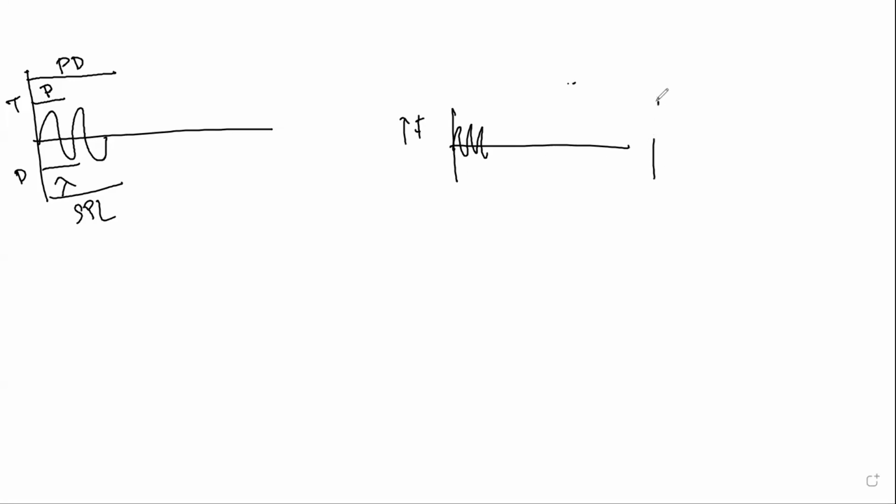So then we have a low frequency. Remember, long, low frequencies. Long, low. This is going to take more time to occur, so its pulse length, the distance that it takes up in space, is going to be increased compared to the high frequency. If we increase our frequency, this chart is going to rotate back this way and look more like this. That means our period decreases, our pulse duration decreases, our wavelength decreases, and our spatial pulse length decreases, which is good for resolution. Remember, we like very small spatial pulse lengths, very low numeric values.